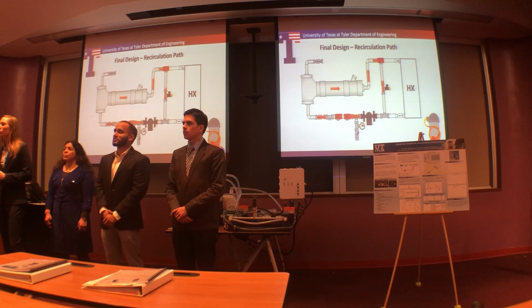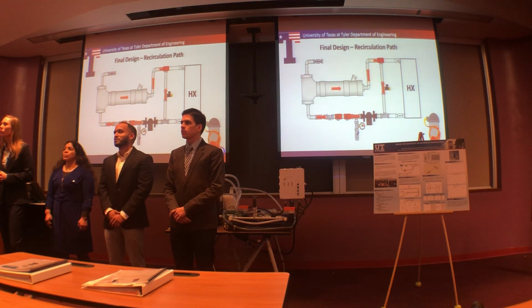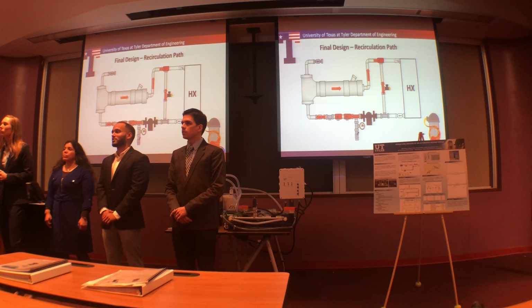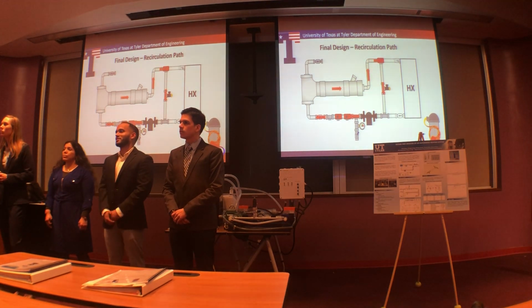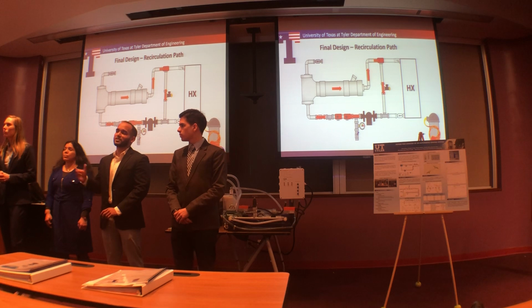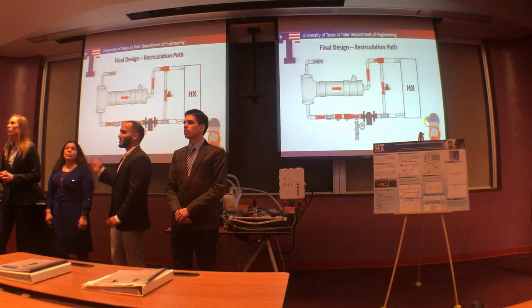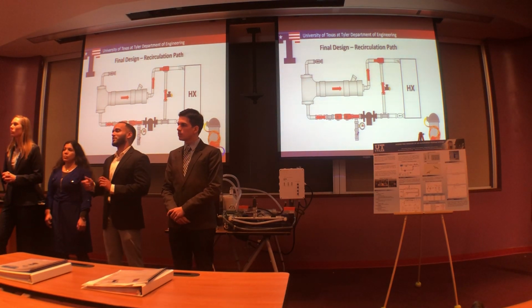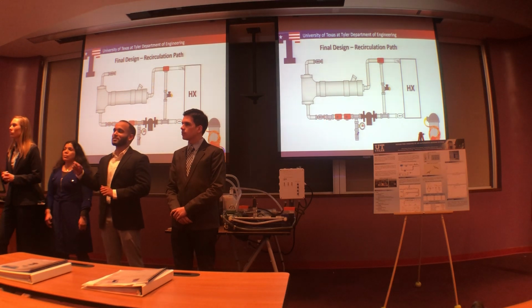So you're not producing any output at that point—during that time you have a low flow rate. We have a disconnect on your stack that I need to understand better: during recirculation, there is no flow rate to the heat exchanger. The heat exchanger flow rate only starts once the desired temperature is reached.